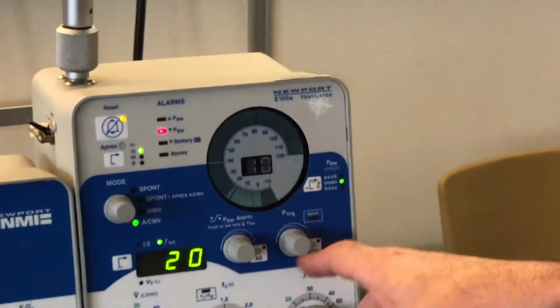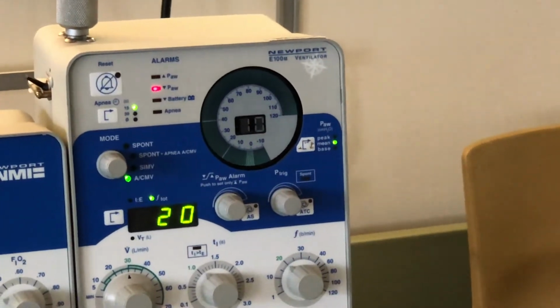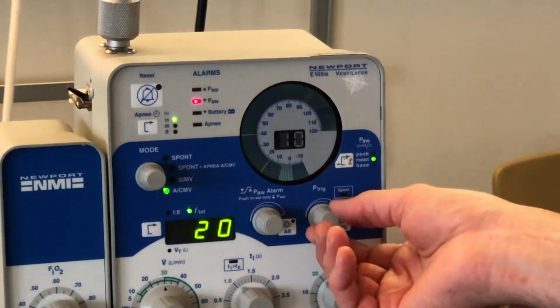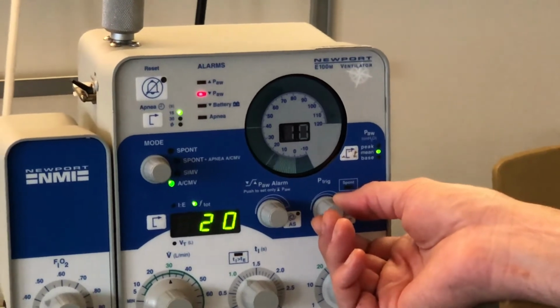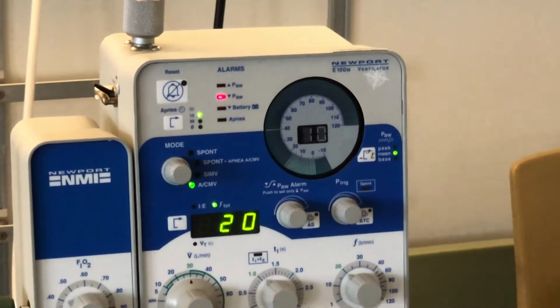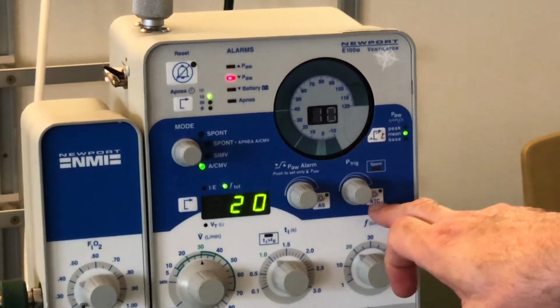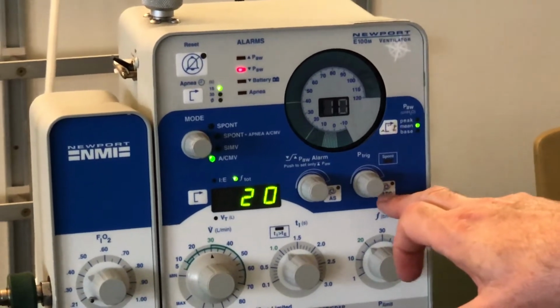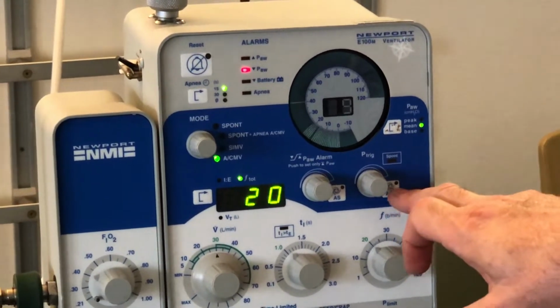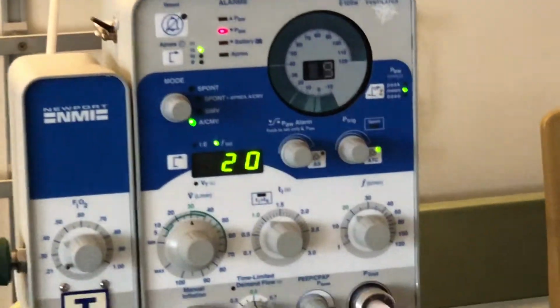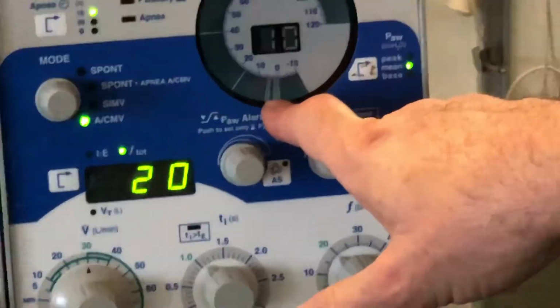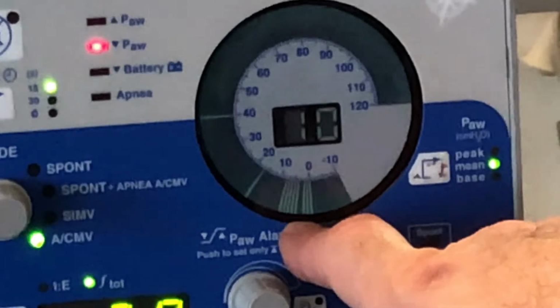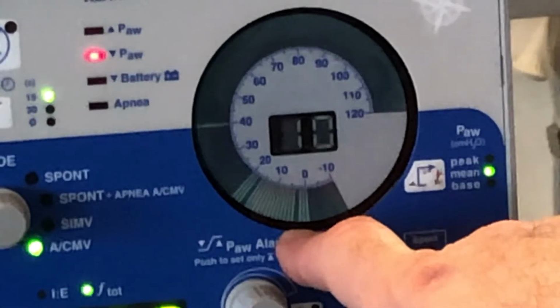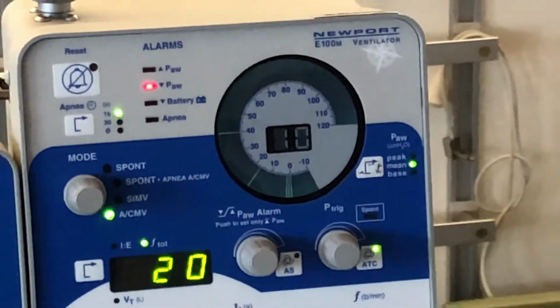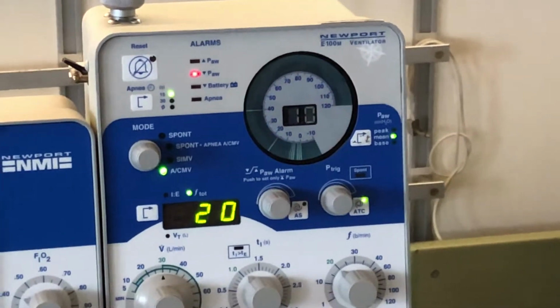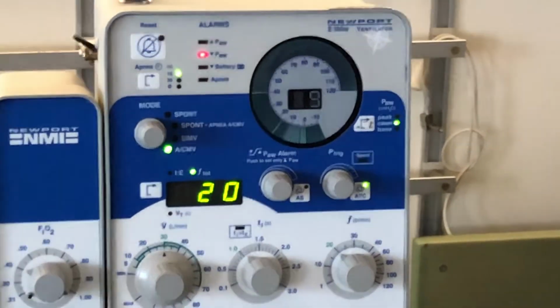The next setting we have over here is the trigger for the machine. So that's for the machine to be able to detect patient effort. And again, if we want to, we can use the automatic trigger control on the machine. So the machine will set the trigger automatically. So if I push the automatic trigger, you'll be able to see the little trigger bar there in the bottom of the pressure manometer. And every time the pressure then drops to that level, the machine would detect a patient effort.